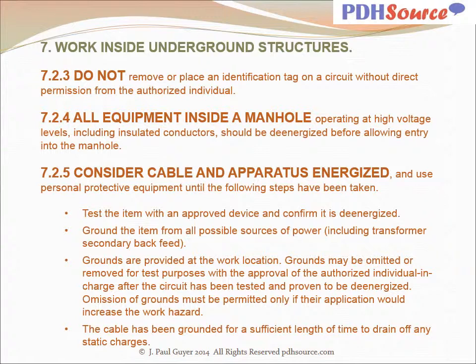All equipment inside a manhole operating at high voltage levels, including insulated conductors, should be de-energized before allowing entry into the manhole. Consider cable and apparatus energized and use personal protective equipment until the following steps have been taken. Test the item with an approved device and confirm it is de-energized. Ground the item from all possible sources of power, including transformers, secondary, backfeed. Grounds are provided at the work location. Grounds may be omitted or removed for test purposes with the approval of the authorized individual in charge after the circuit has been tested and proven to be de-energized. Omission of grounds must be permitted only if their application would increase the work hazard. The cable has been grounded for a sufficient length of time to drain off any static charges.